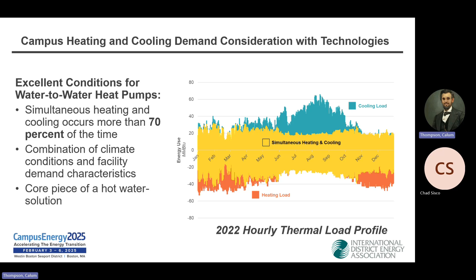We developed a number of different scenarios, in fact 5 different scenarios, which we compared in detail against one another. Each scenario is a different combination of what upgrades are required in the building: does it require steam to hot water conversion, does it require local generation such as an air source heat pump, what's the distribution medium, steam or hot water, and at what temperature, and the configuration of supply equipment, as well as the use of thermal energy storage.